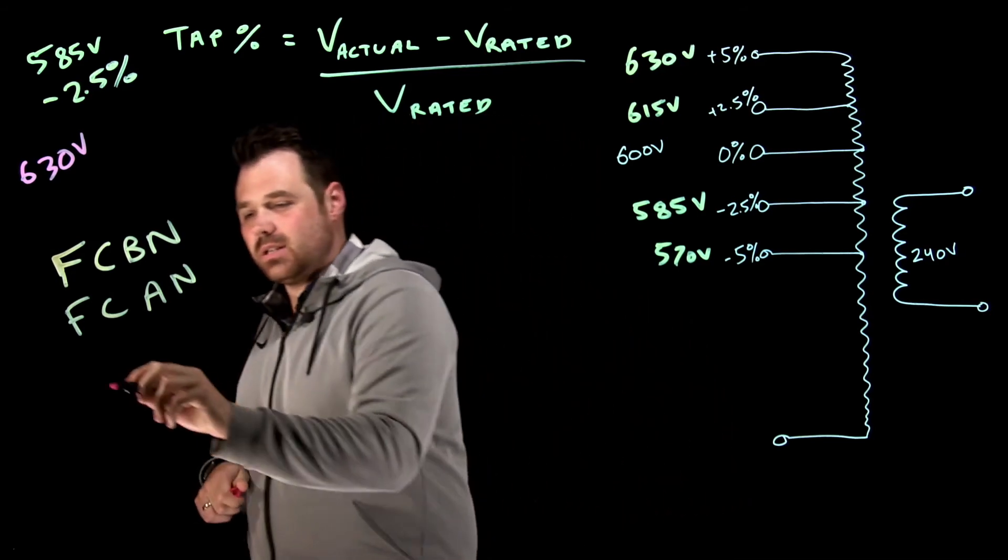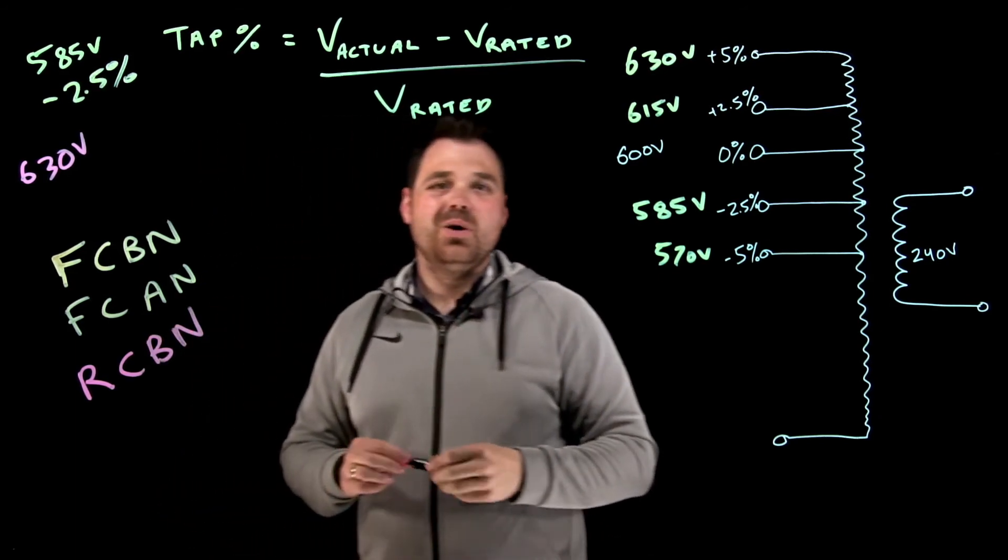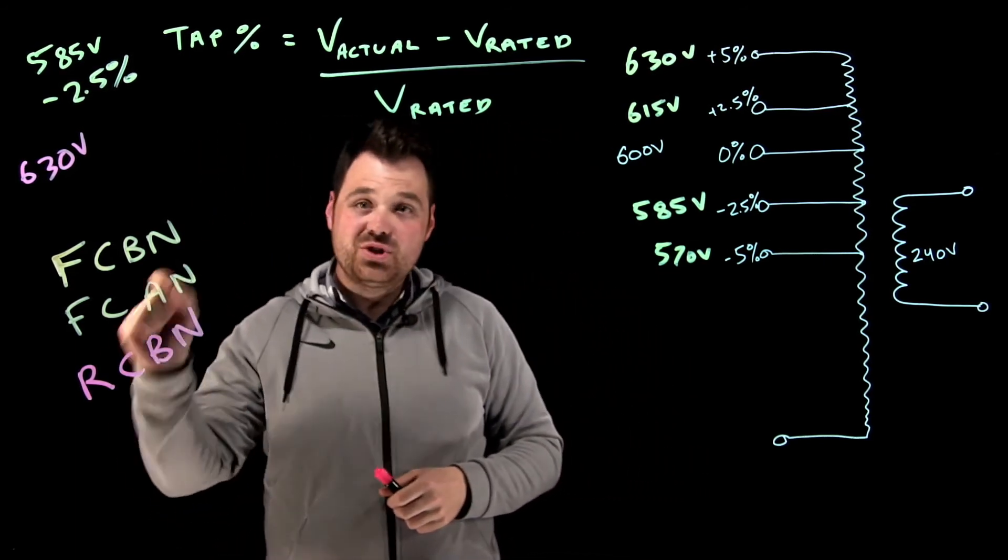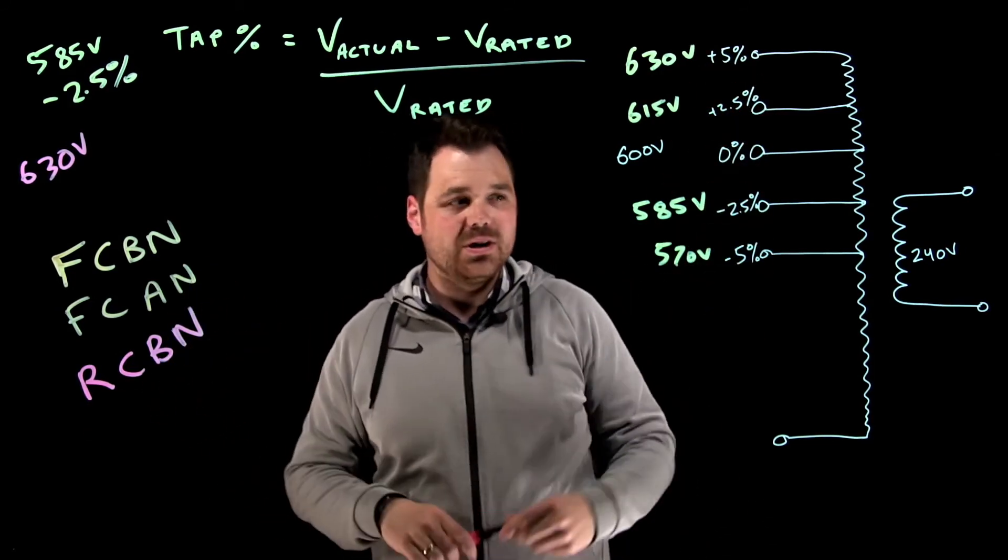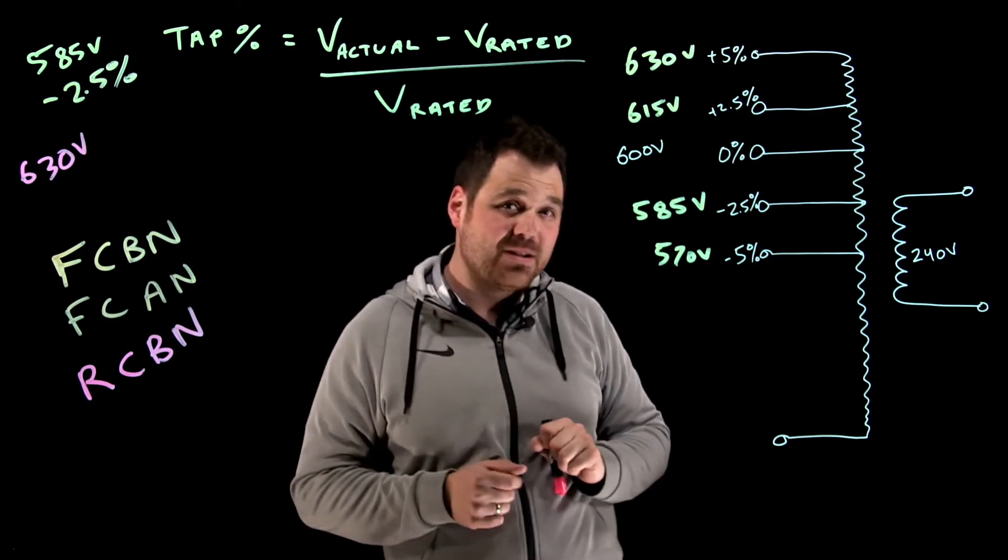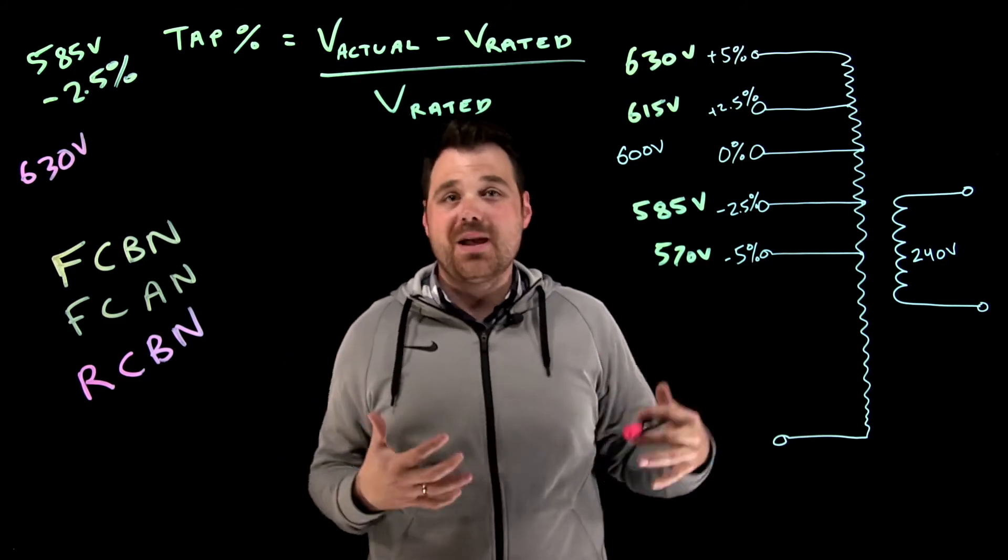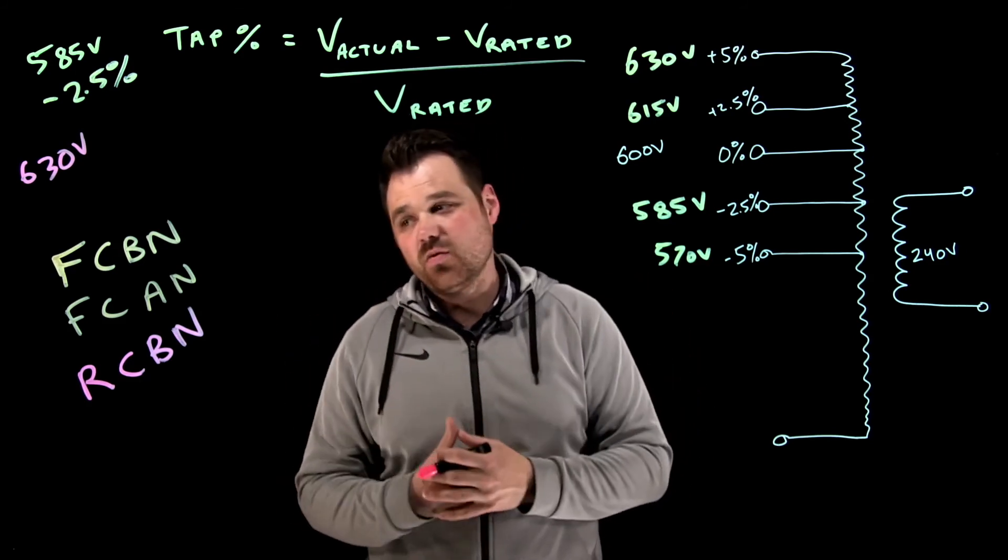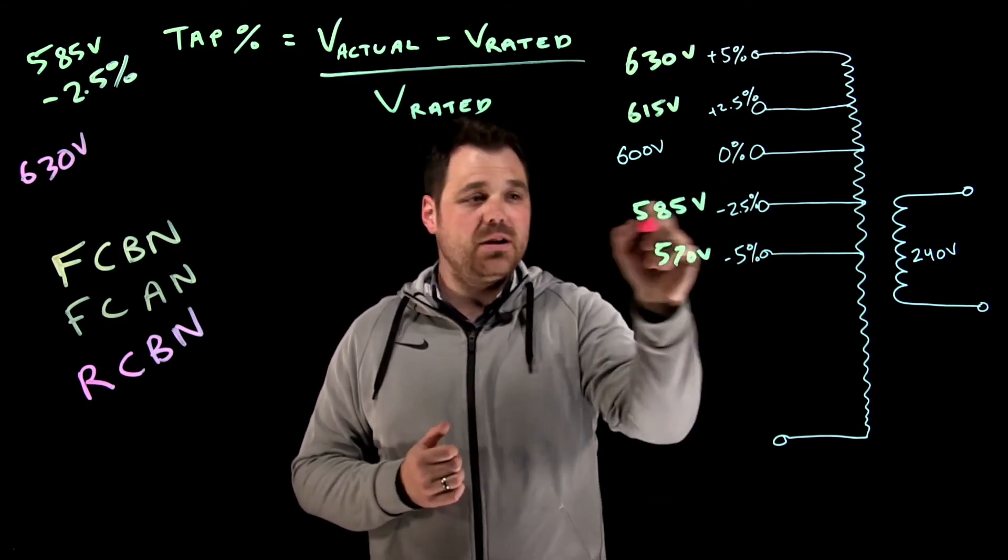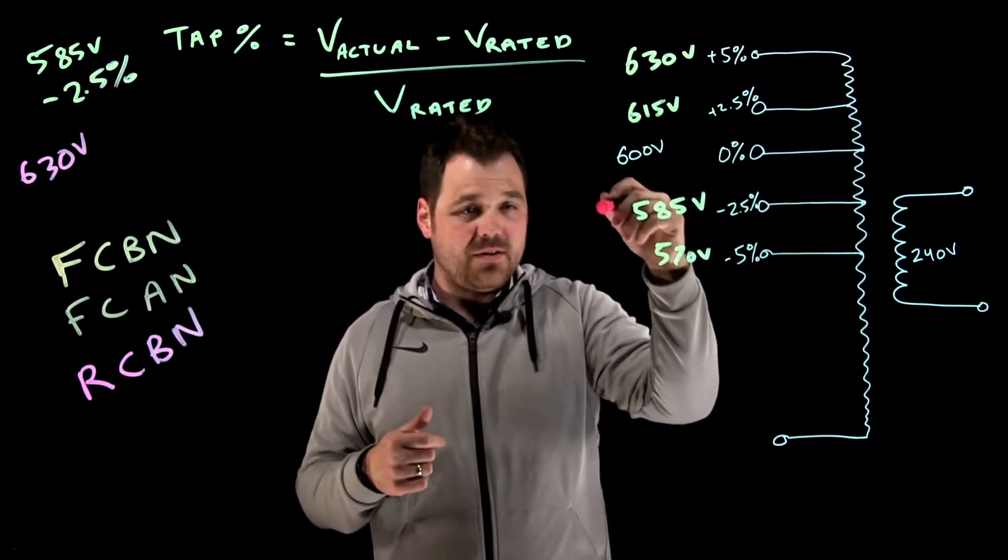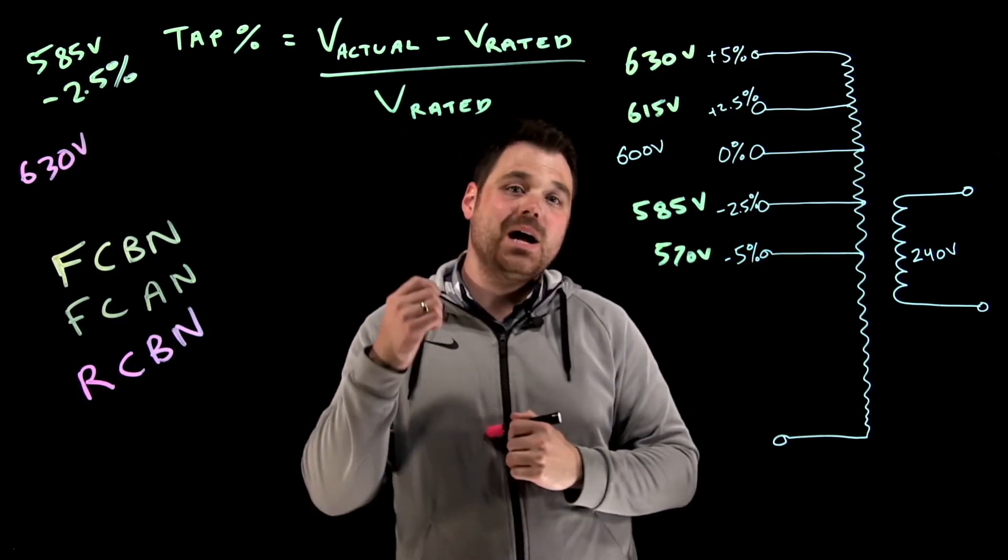What you want to watch out for is the label RCBN, which means it is going to be reduced capacity. If you use a tap reduced capacity below normal means if you apply a tap, your capacity changes accordingly. So that's just different way that they manufacture and that they rate that transformer. So reduced capacity below normal, if I dropped down to two and a half percent tap here, if I tap down to that 585 volt 2.5, my VA is also going to go down accordingly.